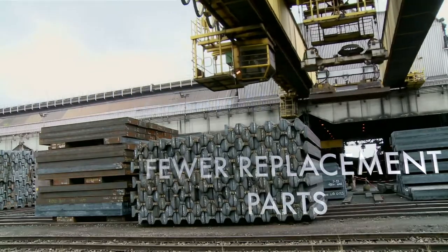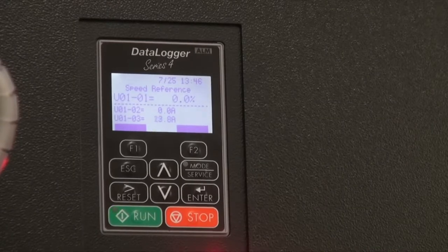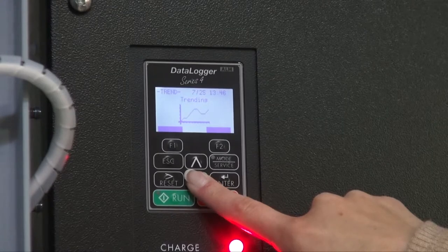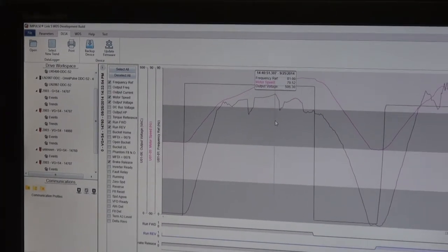The DDC Series 2 comes standard with Magnetek's Data Logger Series 4 keypad, which allows you to easily access run, fault and alarm histories, as well as drive parameters and trending data. It will automatically collect data any time the drive is running. Impulse Link 5 PC software enables you to make drive changes on the fly, troubleshoot quickly and easily, and monitor the drive in real time from a computer screen.